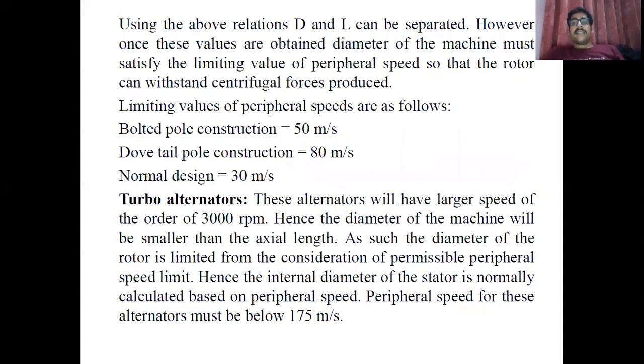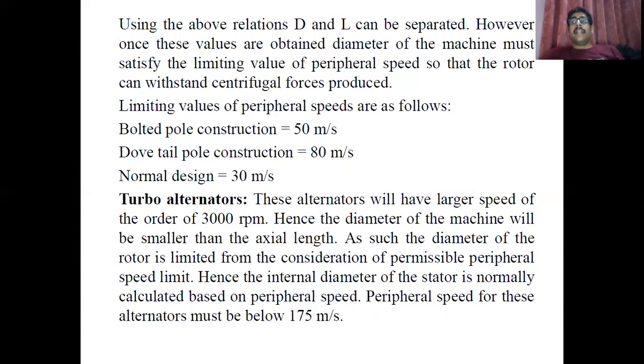Turbo alternators are alternators which have a large speed of the order of 3000 rpm, and these are basically used in generating stations to generate electrical power. The diameter of these machines is small compared to their length, and the diameter of the rotor is limited. In that case, the peripheral speed of the alternator must be below 175 m/s. So if a numerical asks you to design a turbo alternator, separate D and L using peripheral speed Va = π·D·ns ≤ 175 m/s.